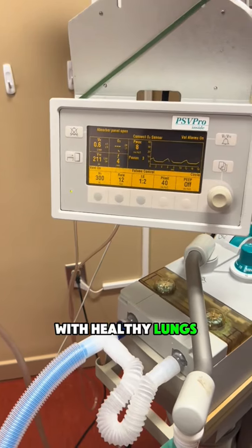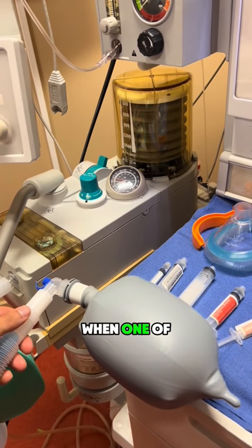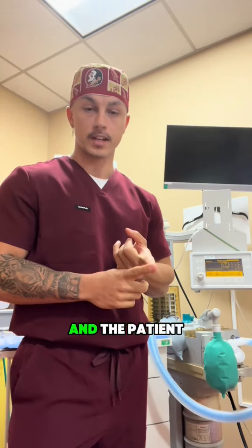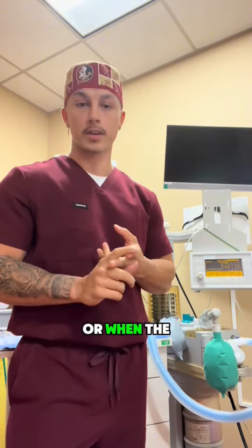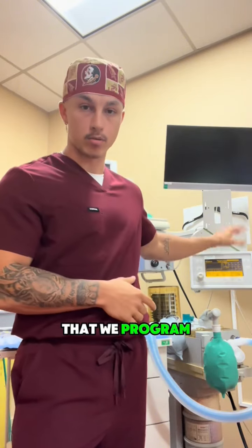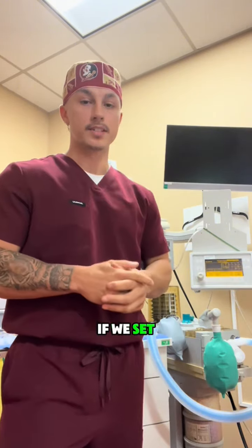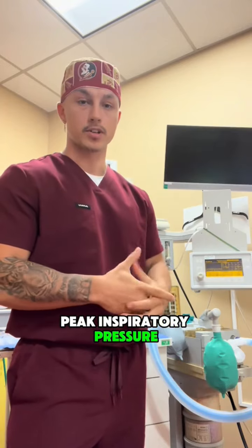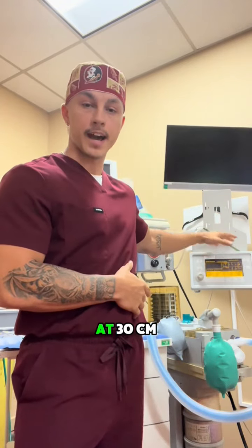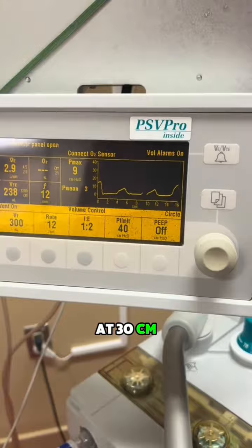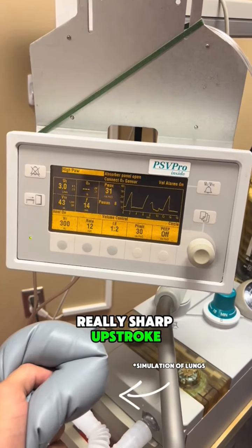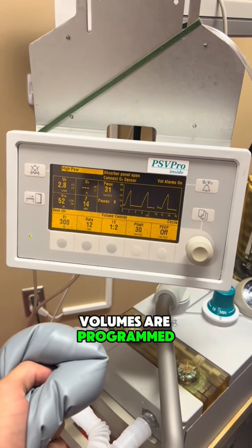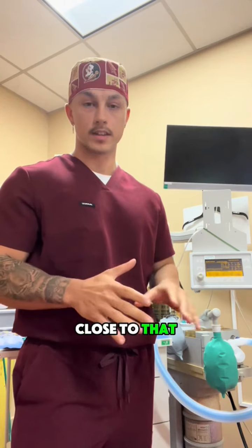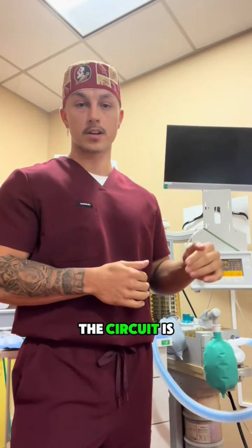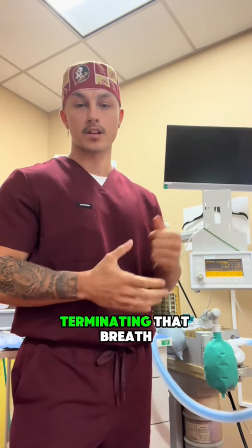In volume control, the ventilator is going to terminate the breath when one of two things happens. The volume is either achieved and the patient gets the full tidal volume breath, or the pressure exceeds a set limit that we program the ventilator to. For example, if we set our Pmax, or our peak inspiratory pressure, to alarm or terminate the breath at 30 centimeters of water, like I'm showing you here, you can see when I squeeze this bag that the pressure shoots up and you have that really sharp upstroke in the waveform. Our tidal volumes are programmed for 300, but we are not reaching anywhere close to that, because the pressure in the circuit is exceeding 30 centimeters of water and it's terminating that breath.